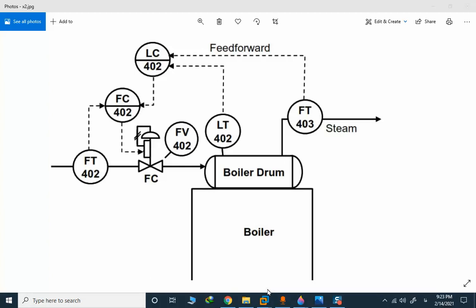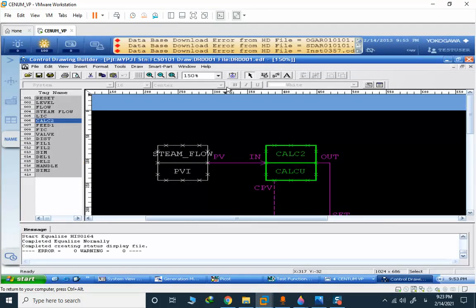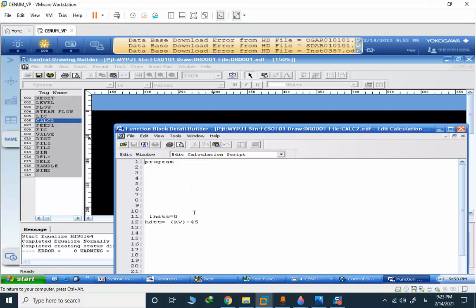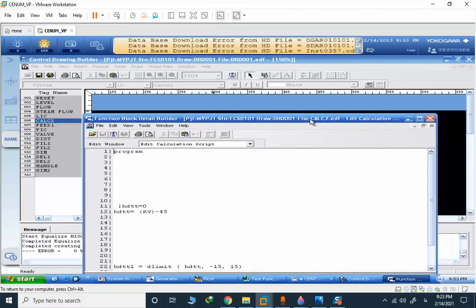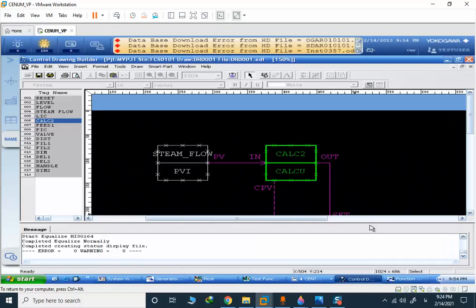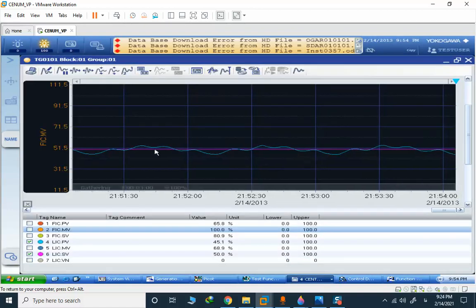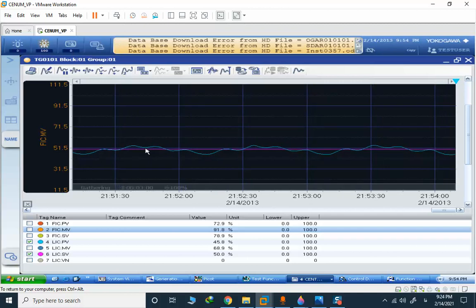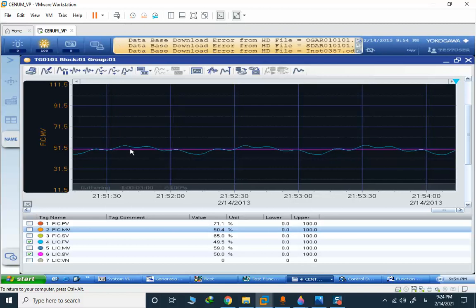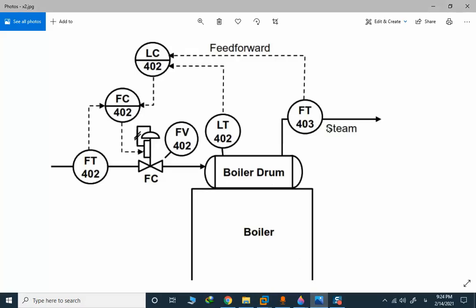In this demo I try to make the difference between enabling and disabling the feedforward application more clear. We have this calculation block — I edited this calculation block. In this case the feedforward is enabled, and you can see that the output, which is the level, is somehow stable because we have the direct effect of steam. The steam somehow depends on the plant consumption or plant demand.